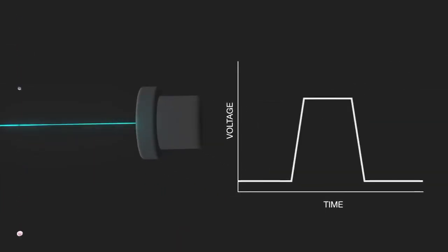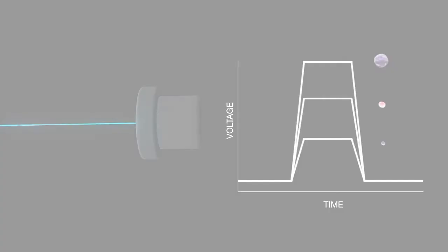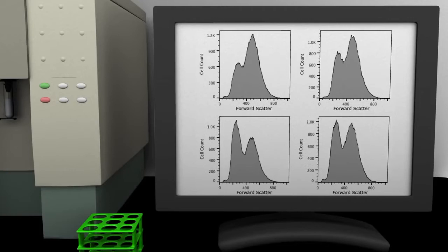The detector converts the scattered light into a voltage pulse which is directly proportional to the amount of forward scattered light. The computer converts these data into a histogram plot with the amount of forward scattered light on the x-axis and the number of cells on the y-axis.